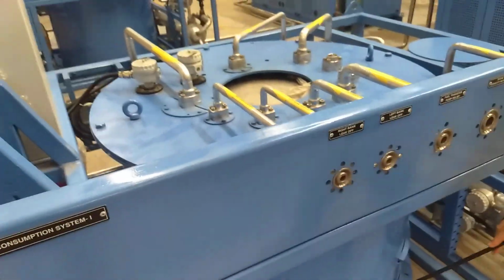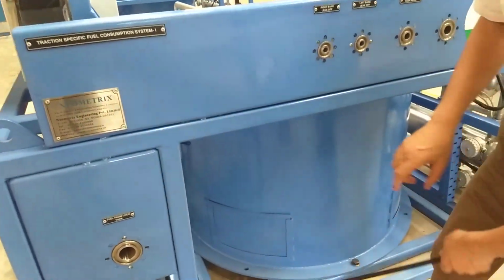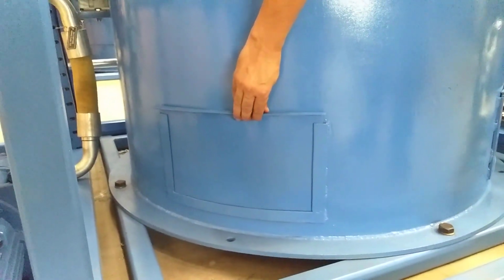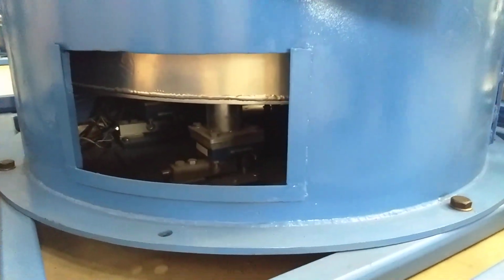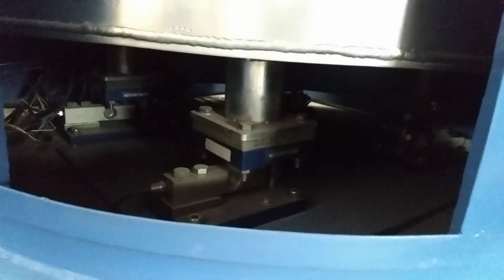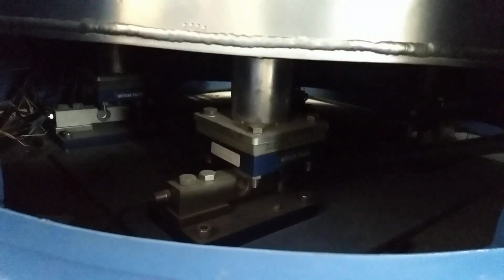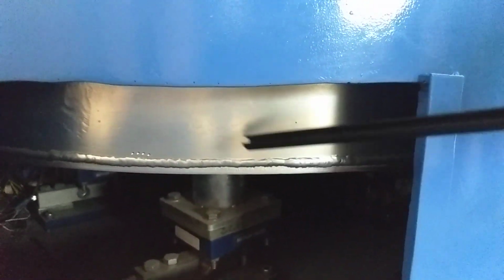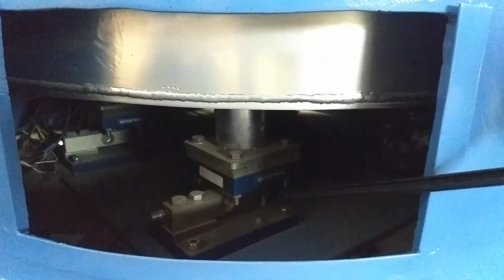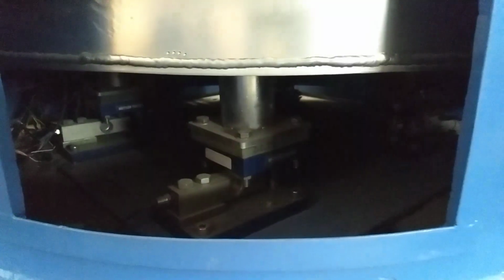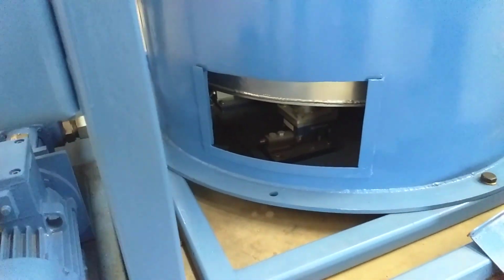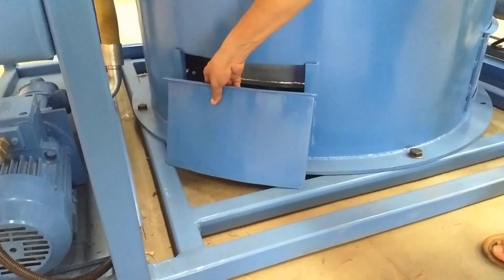I will show you the load cells sitting at the bottom of the tank. I will remove this cover, and you can see the load cells sitting inside the fuel tank cover. This is the Mettler Toledo load cell - there are 4 load cells kept below the fuel tank. This stainless steel fuel tank is freely standing on 4 load cells, which are measuring the weight of the tank all the time. As the diesel in the tank gets consumed, the weight of the tank goes down, and that is monitored by our tank weight measurement system - that is how the consumption is monitored and recorded.